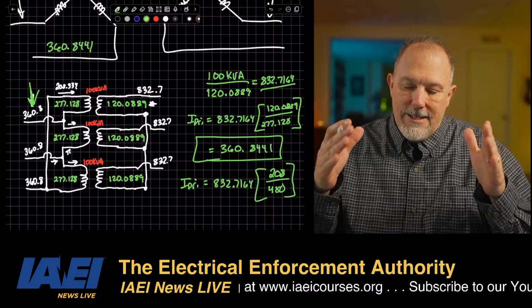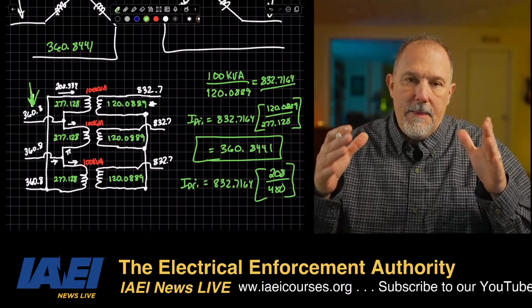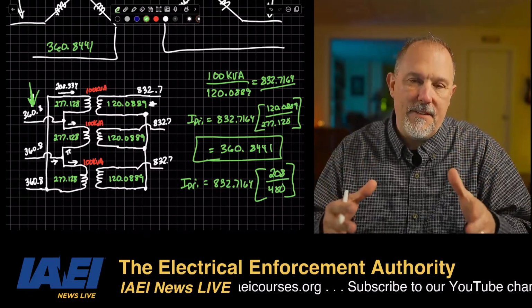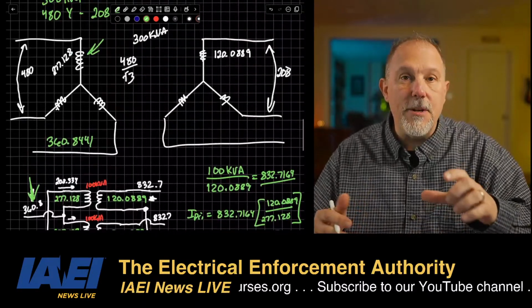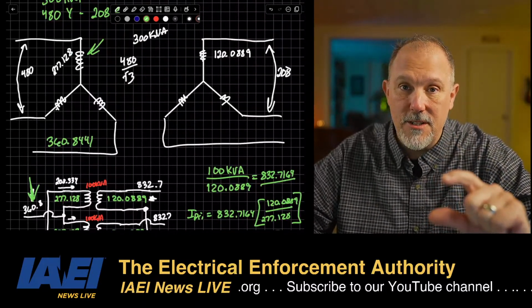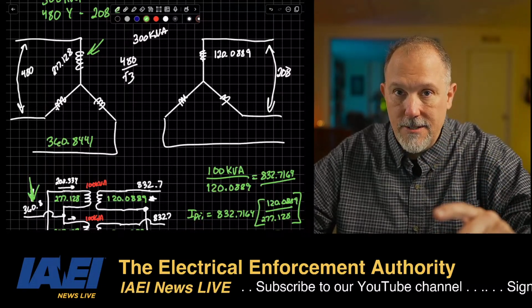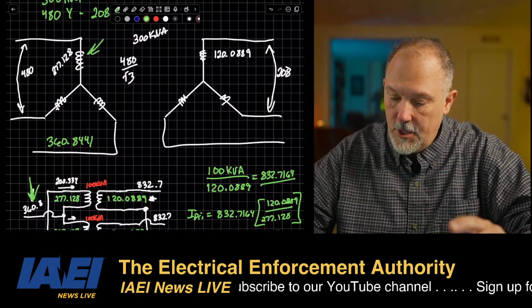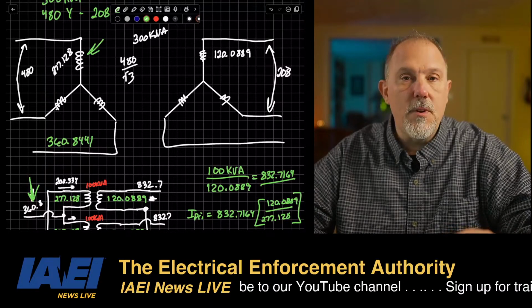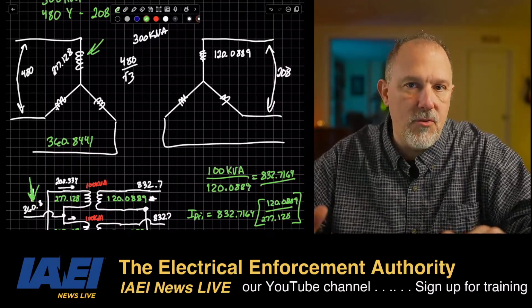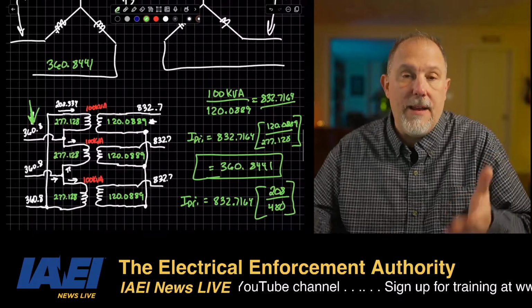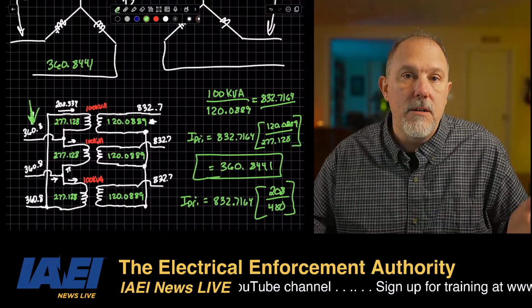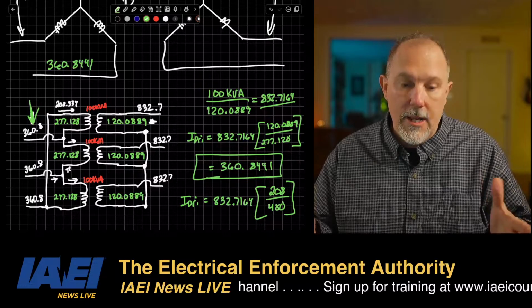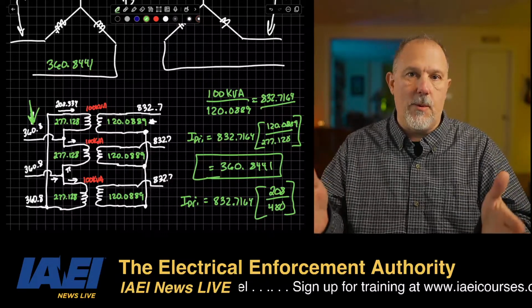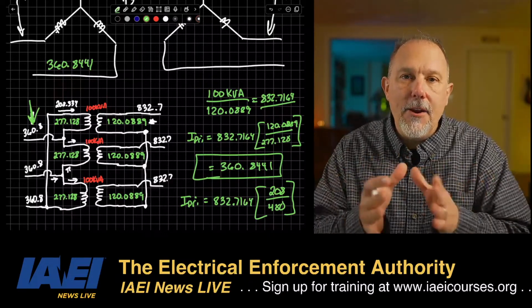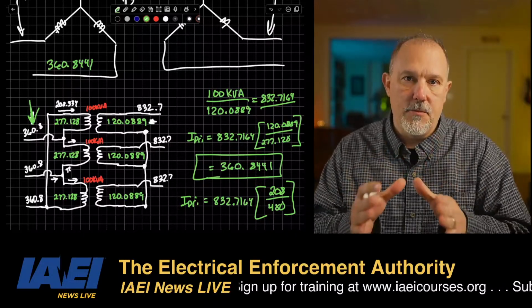So the math makes a difference. Understanding the configuration, using the right voltages makes a difference. You can stick with the rounded numbers, the 120 versus 208. You just saw the difference. 360.74 instead of 360.84 by simply using 277 and 120. The error in difference is negligible.